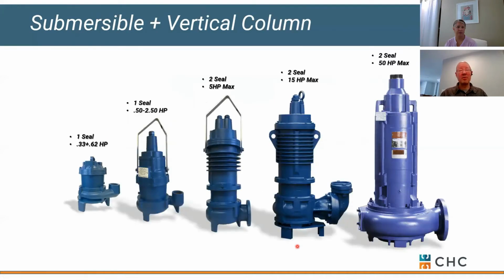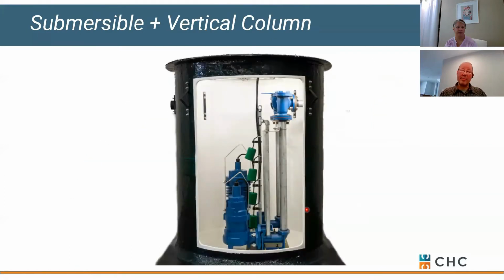We're just going to talk roughly about 2 different pump types for sump and sewage. One is submersible, which we've been discussing all along here. And that simply means that we've got a pump that's down in a basin, surrounded by water. And as water builds up, we send it out. We do have options for single and double seals. We'll talk about that in just a minute. A typical application for submersible: up at the top of our basin, we're going to consider that grade, or where our parking lot or concrete floor is. And then down below grade is where our water is coming into our basin. And then we've got pumps in there that are reacting to water level as it relates to float activation to turn those pumps on or off.